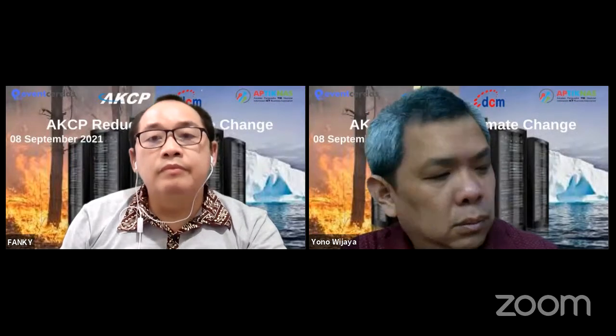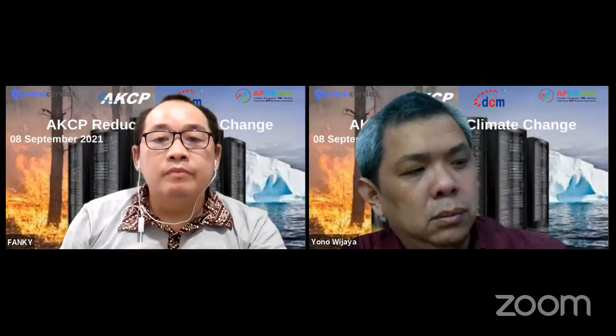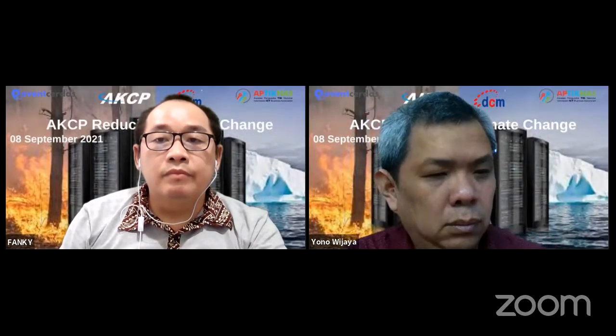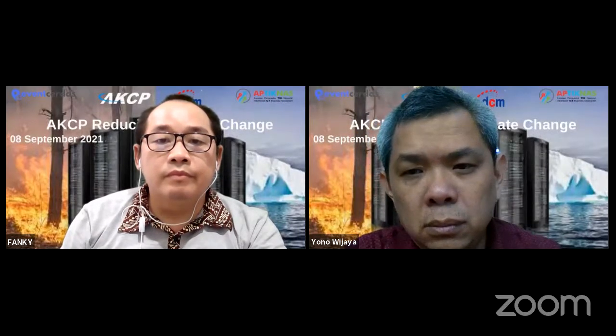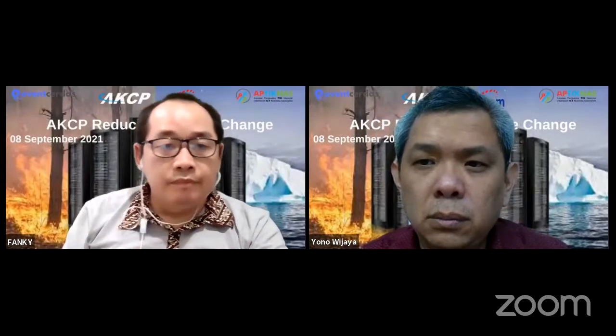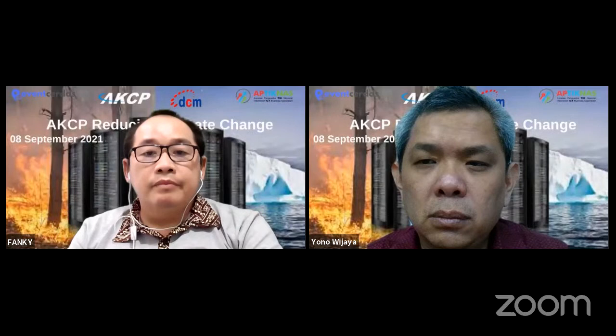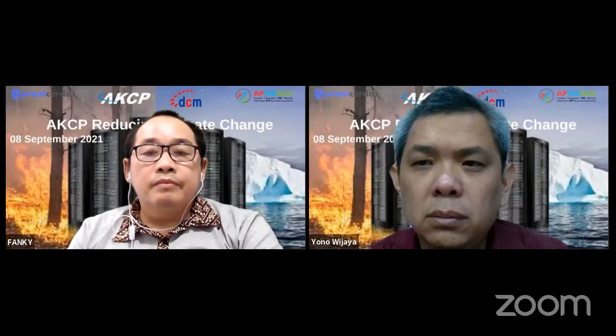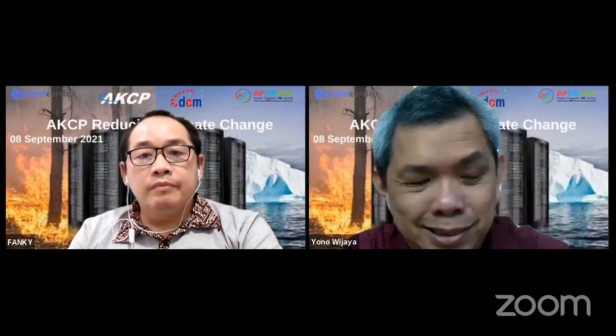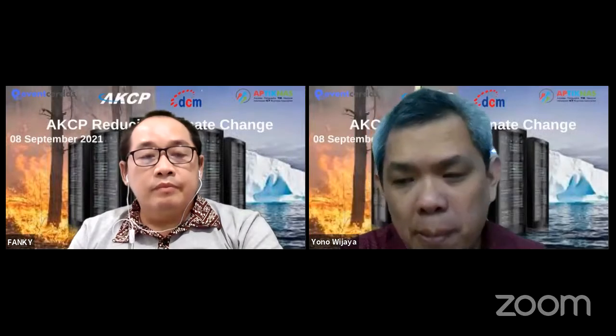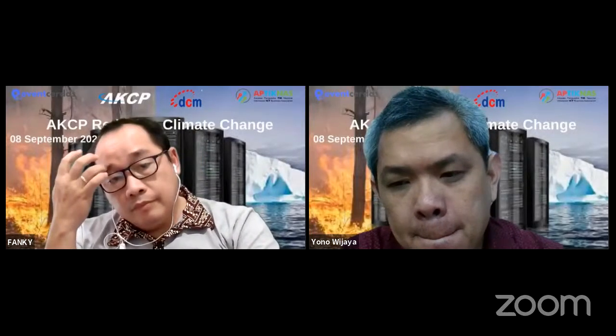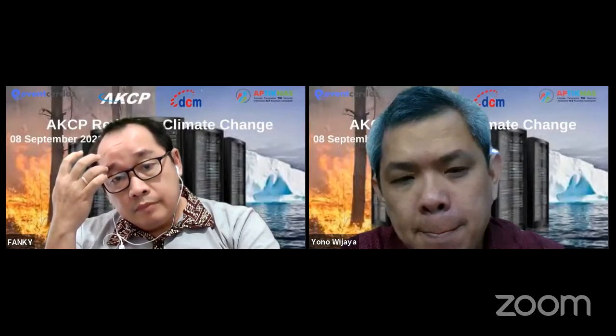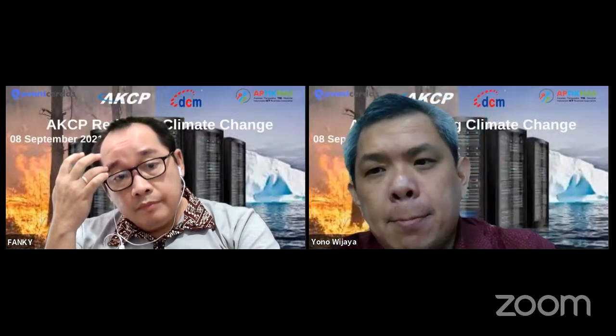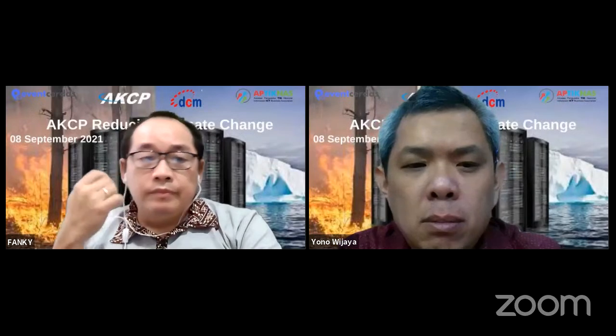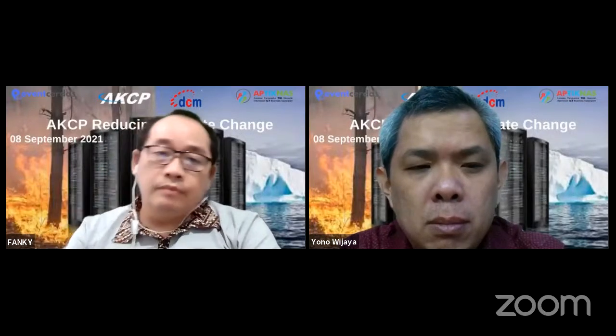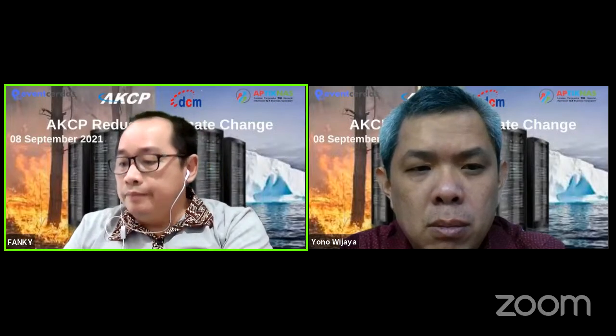The closest I think that anybody has got is a PUE of about 1.1, which factors in, like I say, those additional power usages used for actually sucking the air in, filtering it, and humidifying it. But I have been in data centers. I'm based here in the Philippines, and I went to one in Manila, which is a similar kind of environment to Jakarta when it comes to air quality. And they were bringing in some outside air and not filtering it. And literally there were black marks all over the walls. So yes, you do have to consider making sure that the air is clean when you bring it in. Although in countries like Alaska, Norway, Iceland, the air is already pretty clean, but still there's always going to be some dust and stuff in there that should be filtered out. Yeah, that's a challenge.